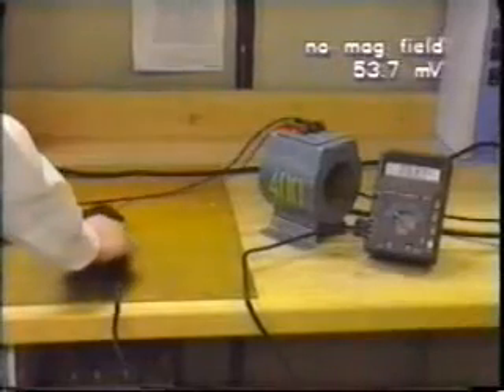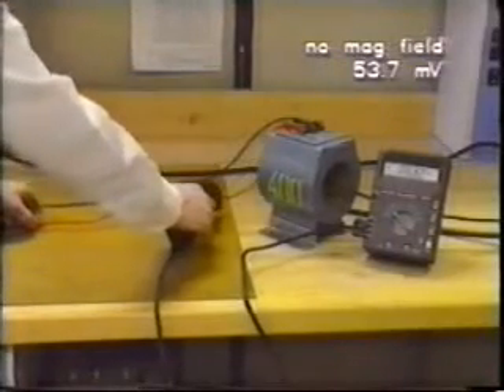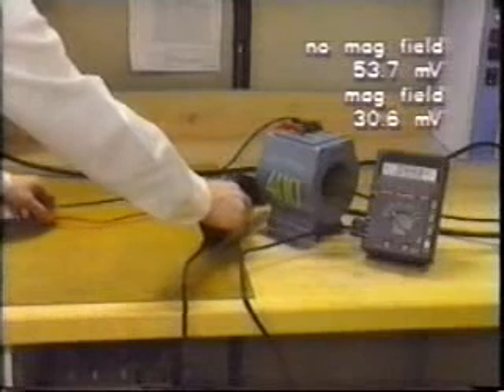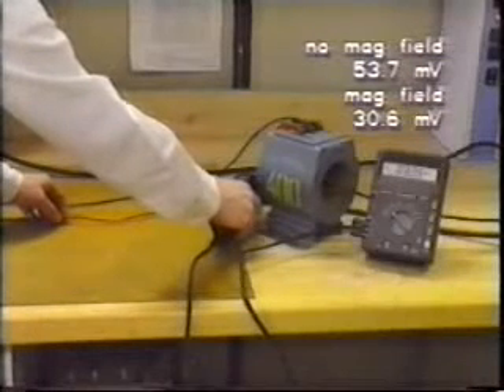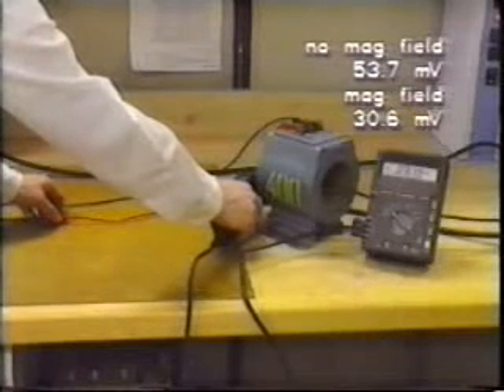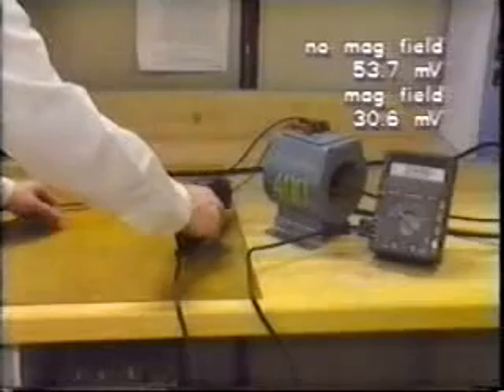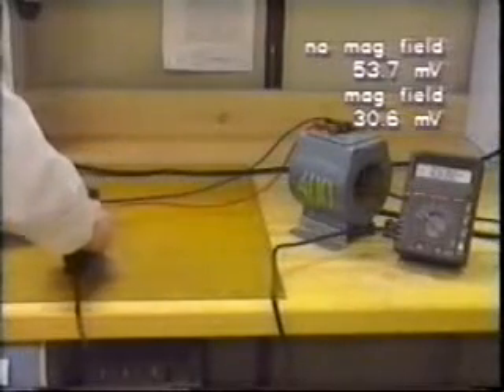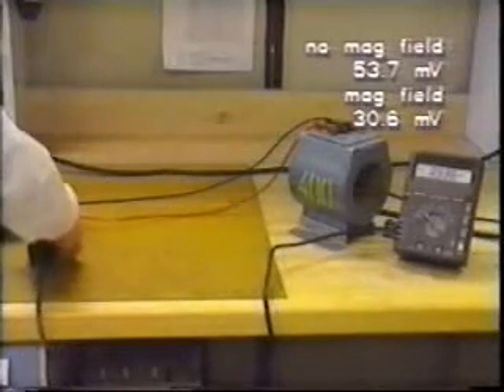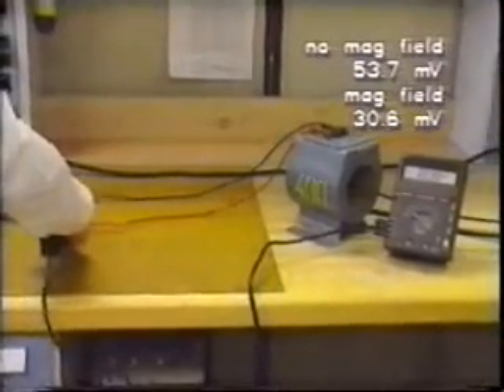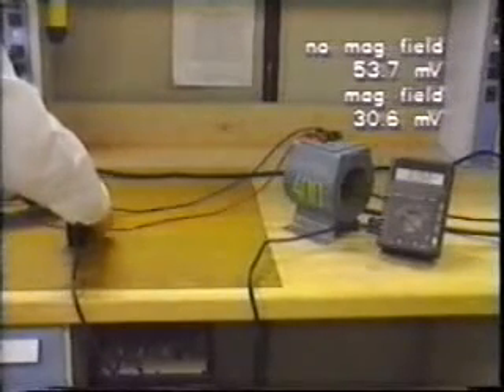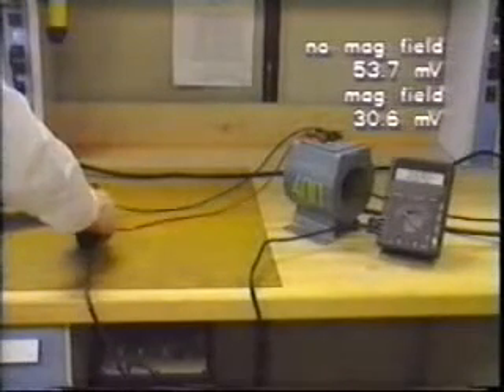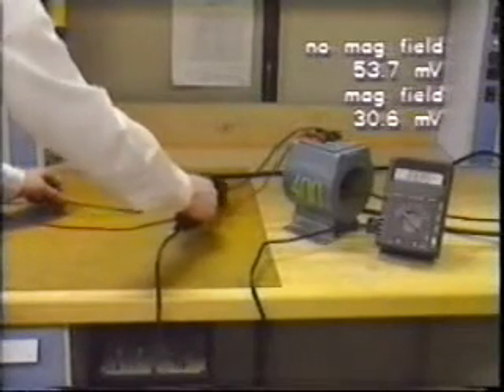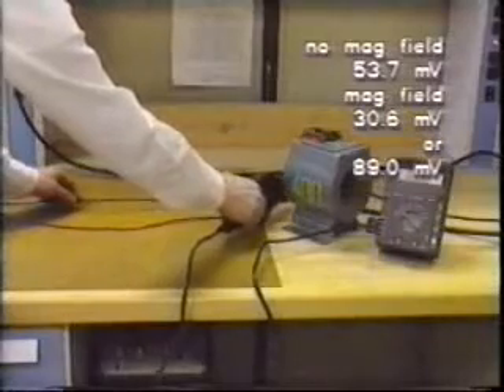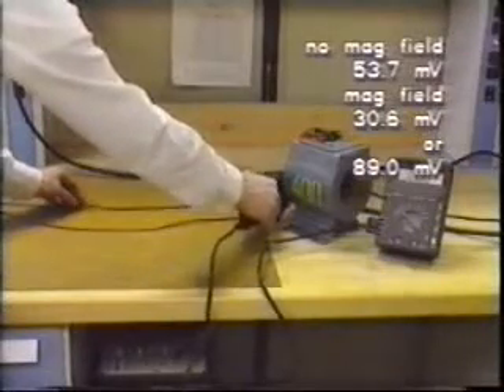In this demonstration, observe the extreme variation in reading as the instrument gets closer to the magnetic field set up by the primary current. Note that this probe is subject to significant error when used in the proximity of magnetic fields from other conductors, for example in switchgear cabinets. It is evident that a magnetic field can significantly affect the reliability of the readings.